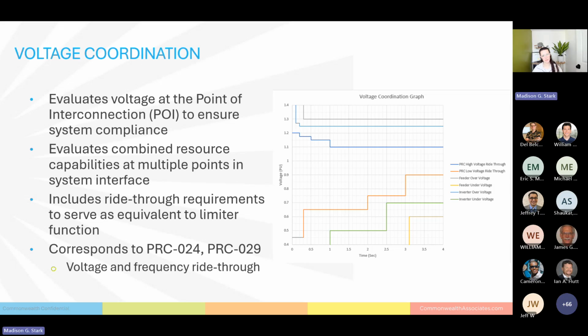Now, if we go down to our undervoltage scenarios, we want to see the same thing. Here we have our low voltage ride through. That's this orange line. The next thing we want to see is this inverter under voltage. This is the inverter's internal controls. Perfect. That's the next thing we want to see. Amazing. And then the last thing we want to see is that overhead system protection, which is the feeder under voltage, which is right here. So perfect. Looks like the system is appropriately coordinated.